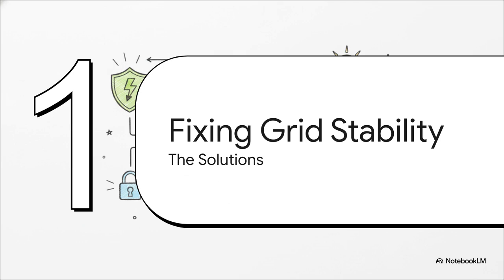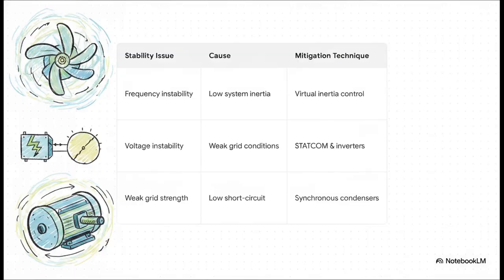Section 3. Fixing grid stability issues. If we're losing our physical momentum, how do we fix it? Engineers actually have some incredibly clever mitigation techniques for this. To fix frequency instability caused by low inertia, they use virtual inertia control, basically programming inverters to artificially mimic the momentum of a spinning turbine. For voltage instability, we use StatComs and grid-forming inverters. And to fix weak grid strength caused by low short-circuit capacity, we literally install large spinning motors called synchronous condensers onto the grid. They don't generate any power. They just sit there and spin to provide that missing physical inertia and reactive power support.